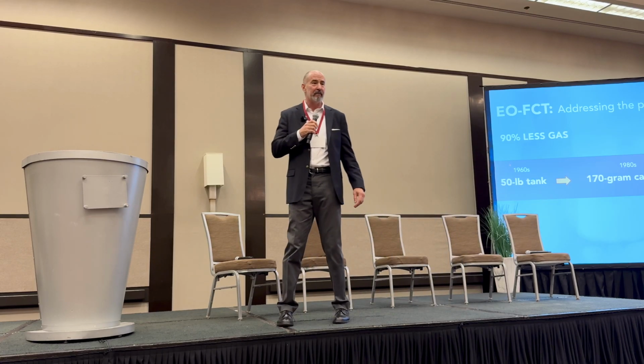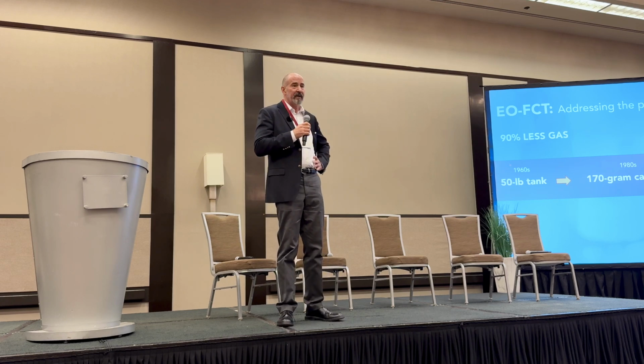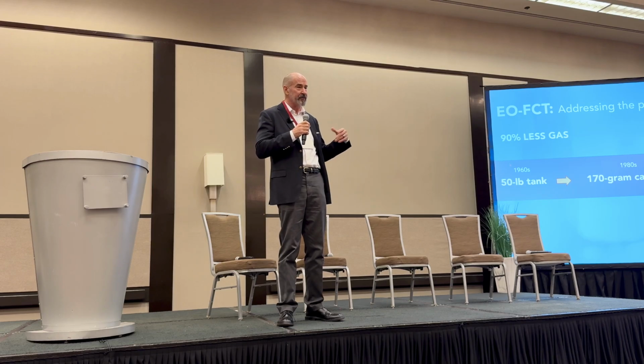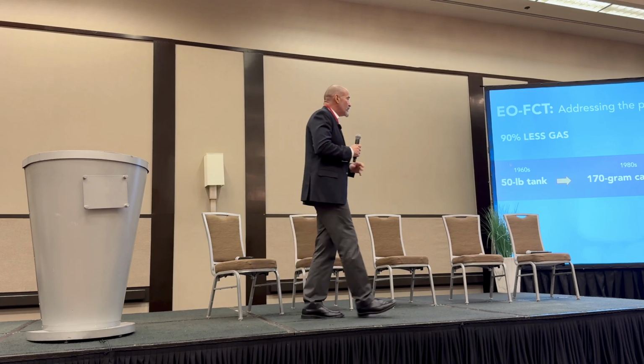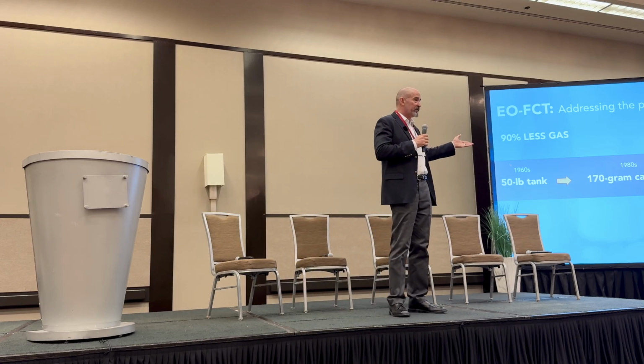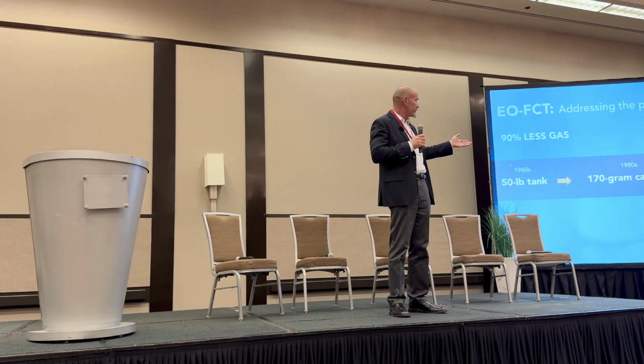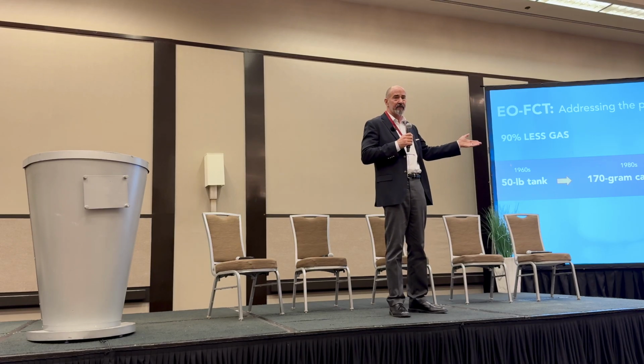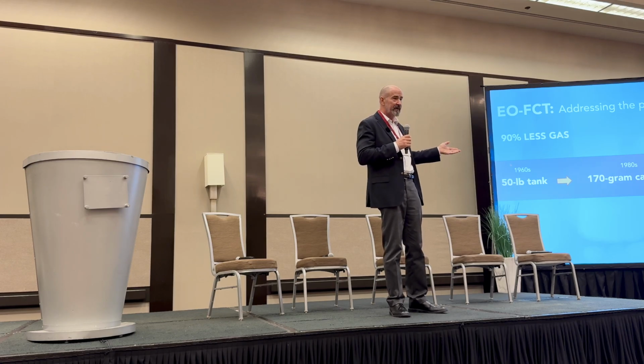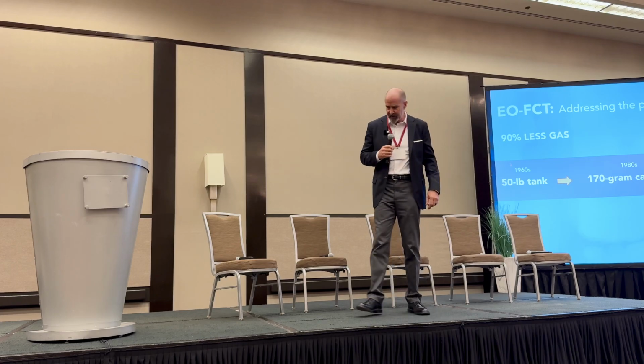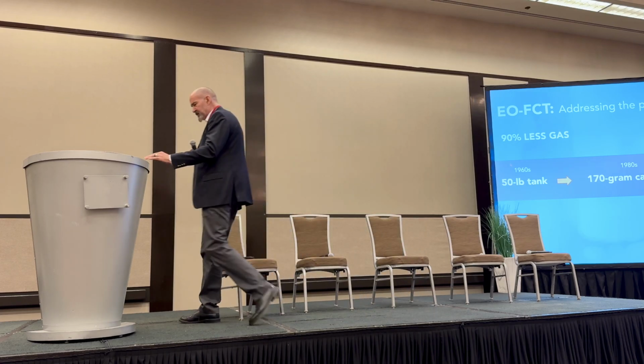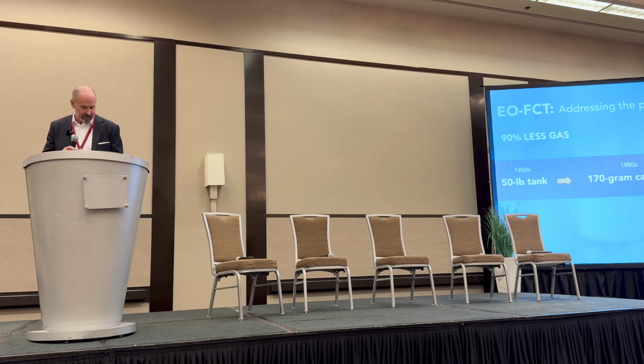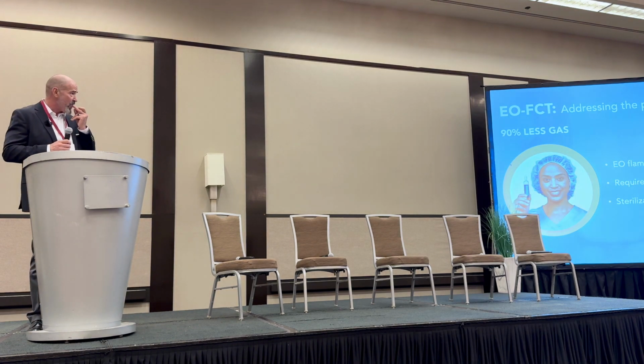The manufacturer recommended ventilated storage. And if you were working in a department, you would have ethylene oxide monitors go off if the ventilation was not effective. What we have done with our recent system, with the flexible chamber system, is reduce that further. We're using only 17.6 grams of gas per cycle. And you can see here the steady evolution in the efficiency of ethylene oxide. This has not been a static technology.